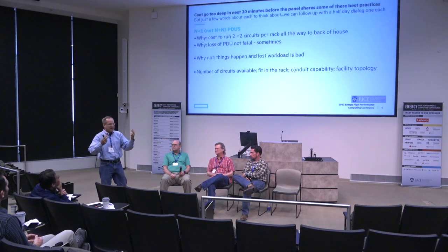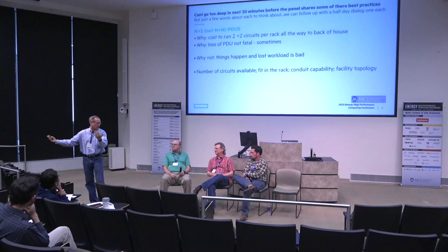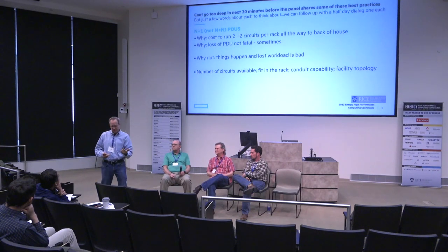So today, I think everybody in U.S. data centers can tell the story that they can do 35 kilowatts of A and 35 kilowatts of B at 415, 240, or even 208 Delta. But as power is going up, it's not going to happen. I mean, how many of your facilities are going to want to bring in the fifth whip or the sixth whip if you want that?